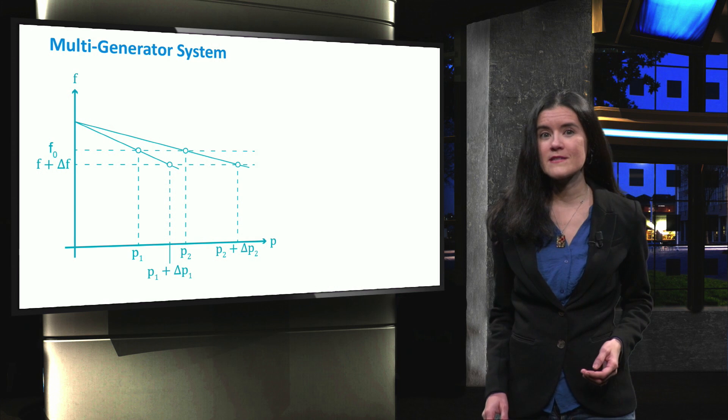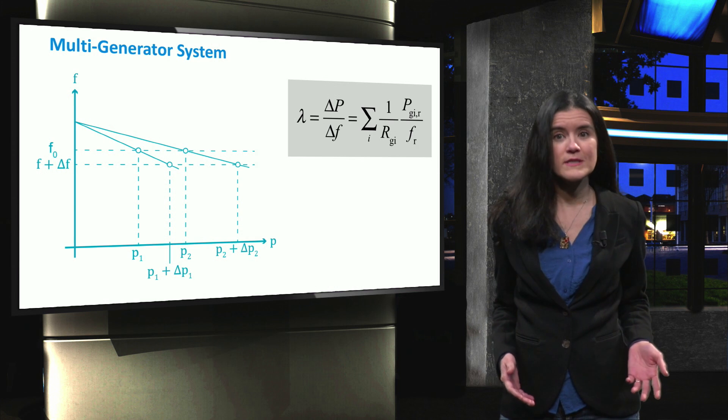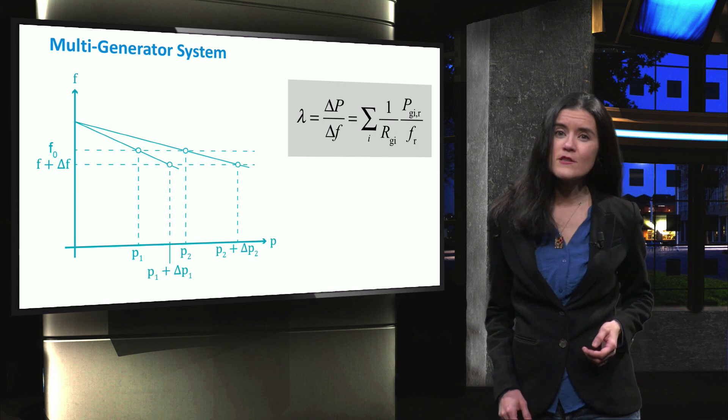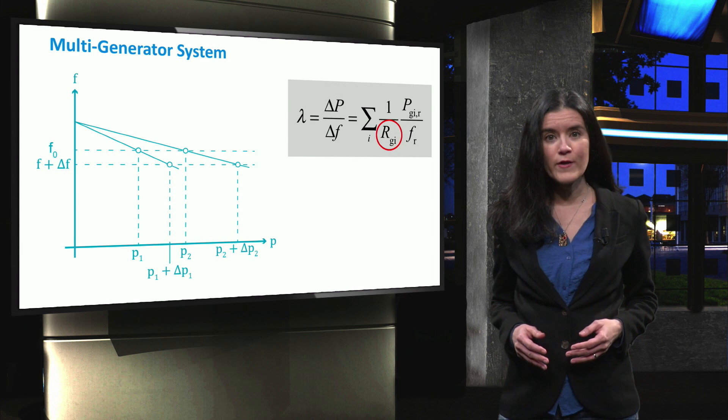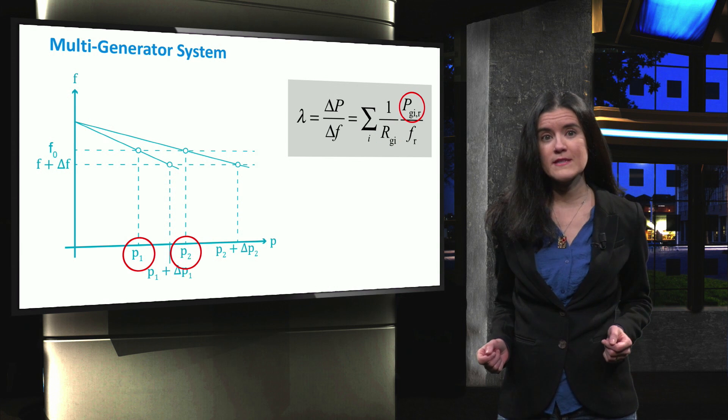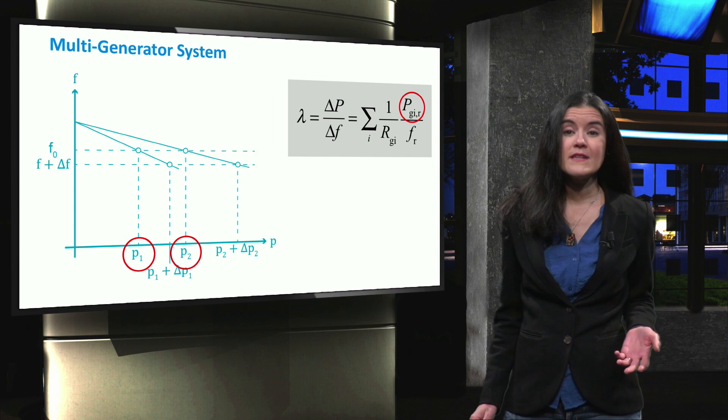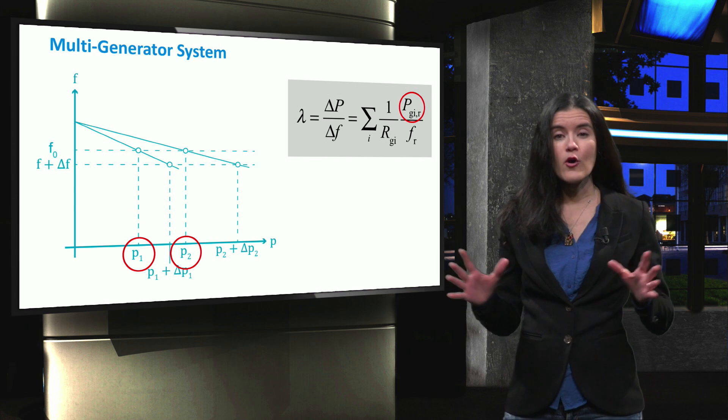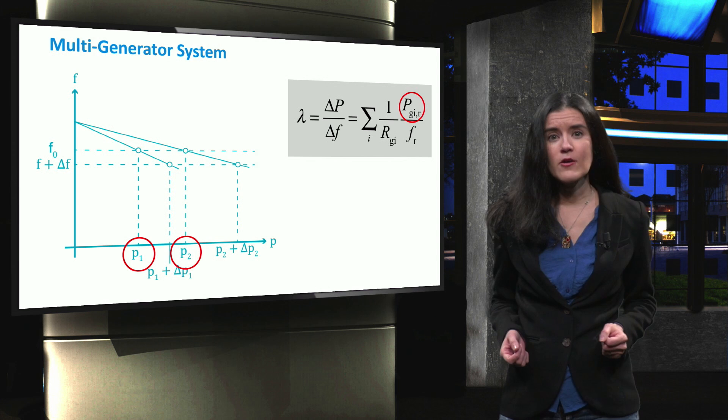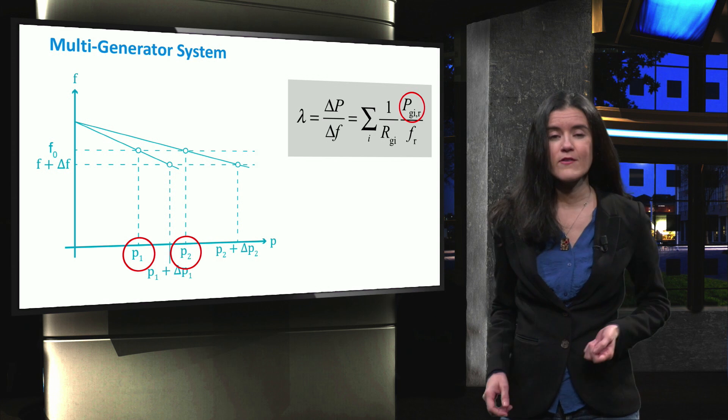For a multi-generator system, the network power frequency characteristic given by lambda is determined by the droop and the nominal rated power of all generators in the system. In this case, a change in active power consumption is met by all generators, given as the combination of all droops, as shown in the equation.